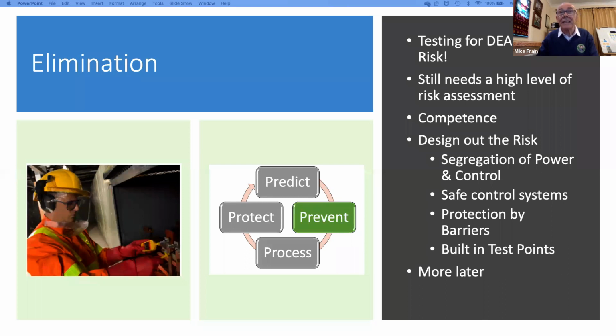Elimination: testing for dead in order to make safe. It can expose a person undertaking isolation to the hazard. And it's a bit of a thorny issue, actually, and it's something I deal with a lot in the book itself. Again, there's 7 pages on just testing for dead, because it does carry a risk. It still needs a high level of risk assessment and competence of the individuals. And we can start to think about designing out the risk through segregation of power and control, by safe control systems, protection by barriers, built-in test points and so on. But there's a lot that the individual can do to protect himself.